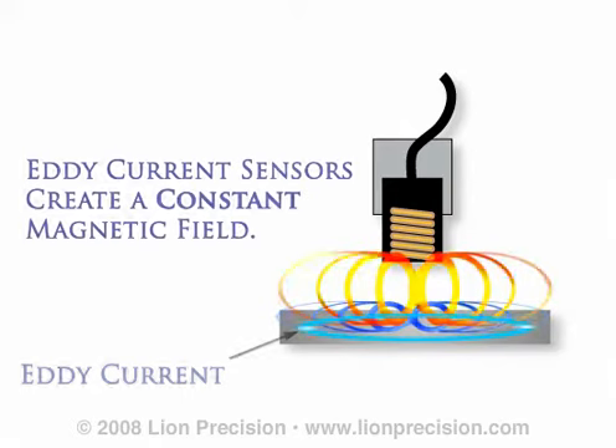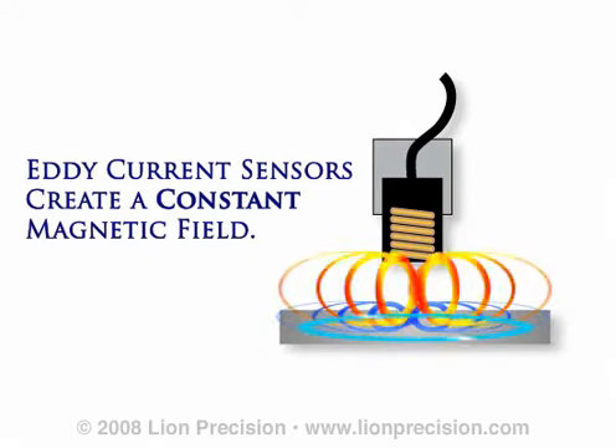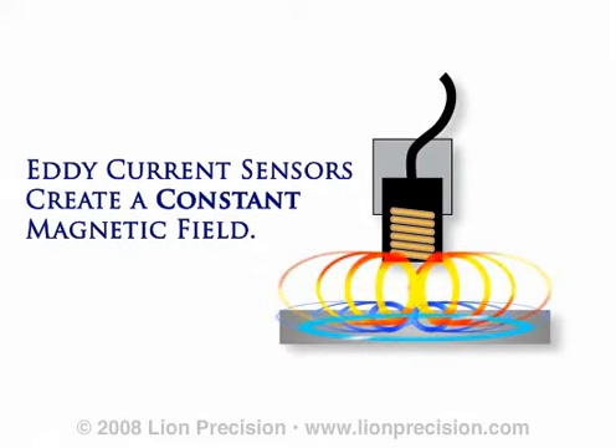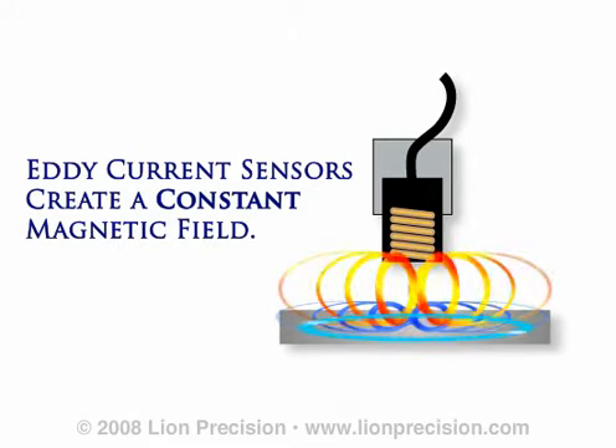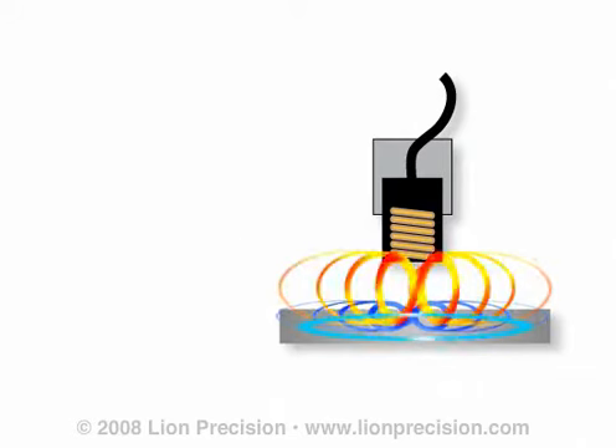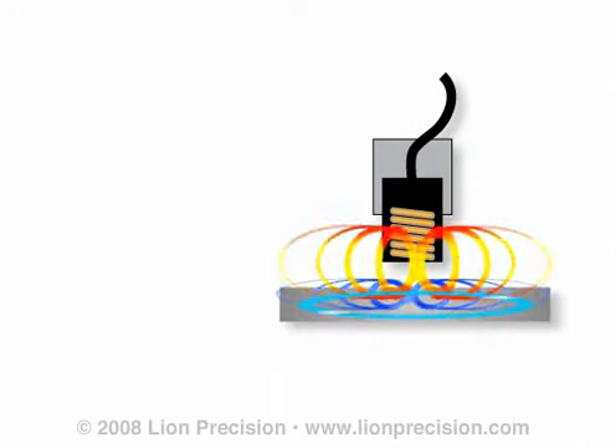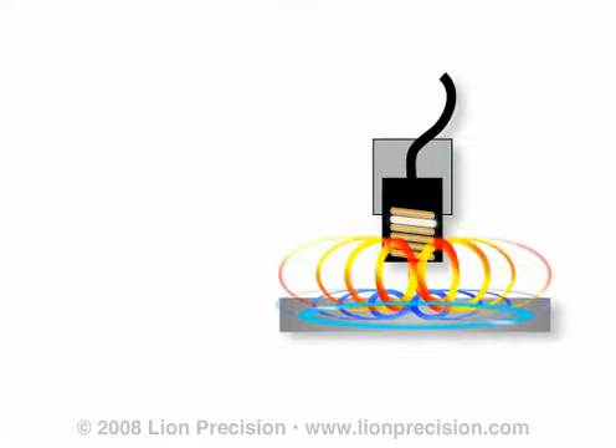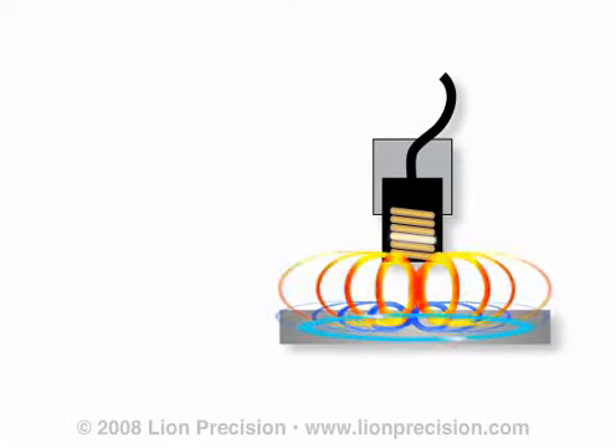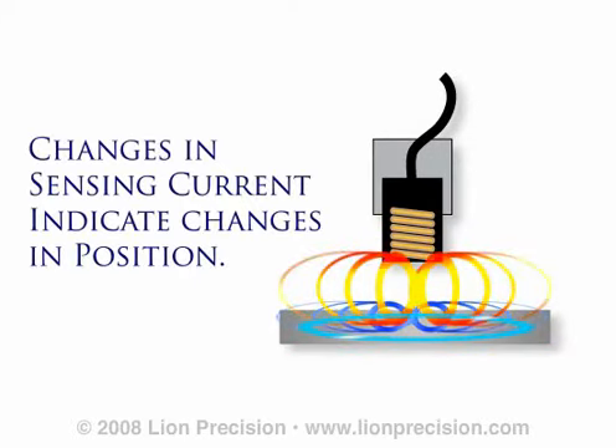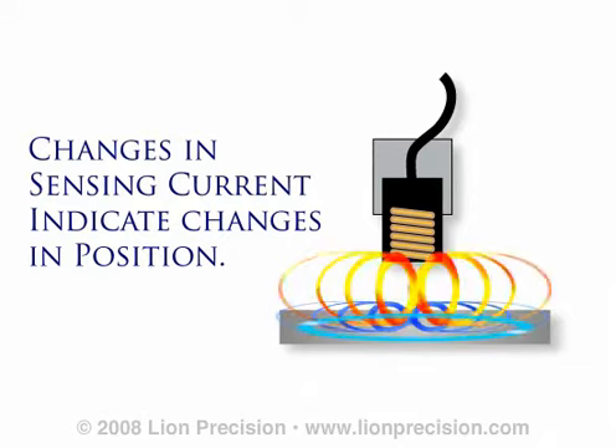The sensor is designed to create a constant magnetic field around the sensing coil. As the eddy currents in the target oppose the sensing field, the sensor will increase the current to the sensing coil to maintain the original magnetic field. As the target changes its distance from the probe, the amount of current required to maintain the magnetic field also changes. The sensing coil current is processed to create the output voltage, which is then an indication of the position of the target relative to the probe.